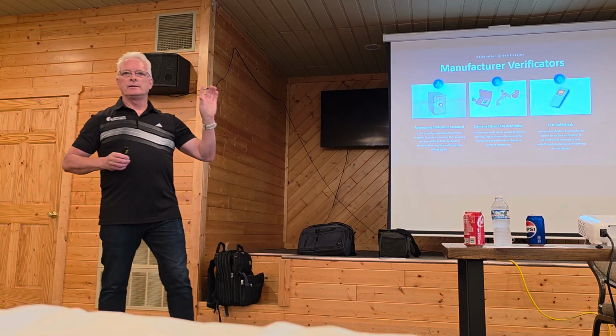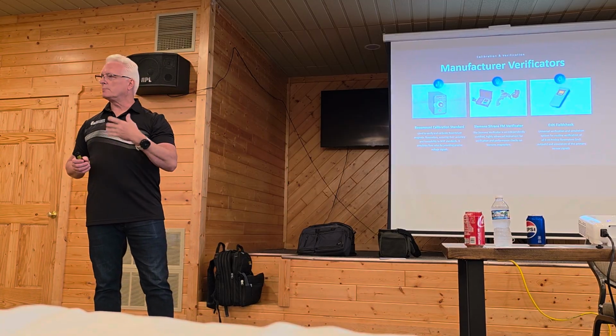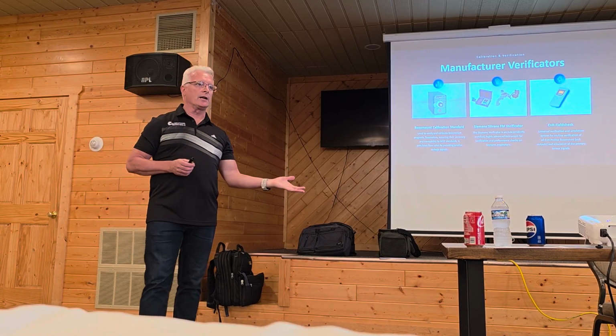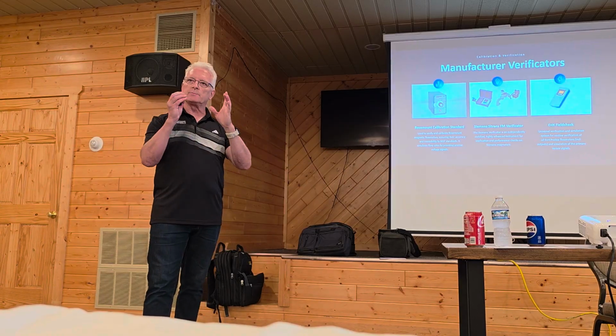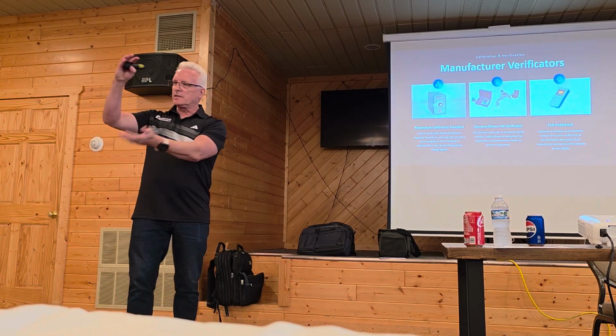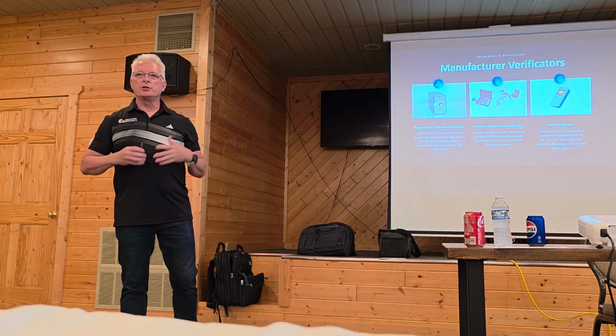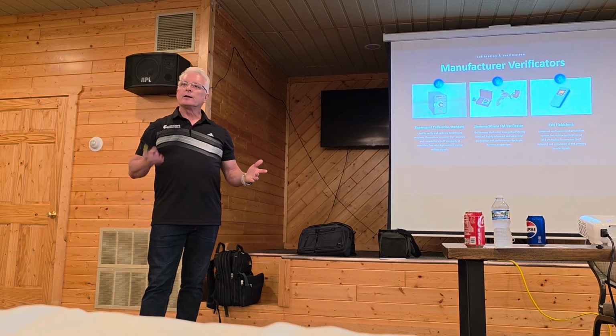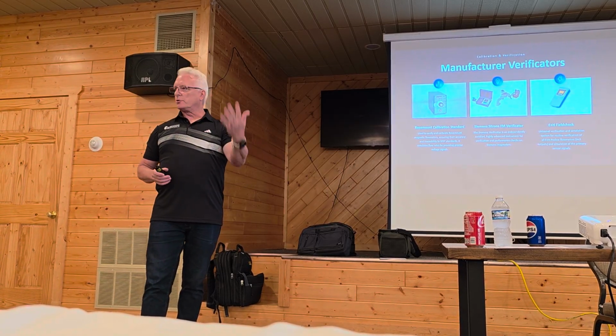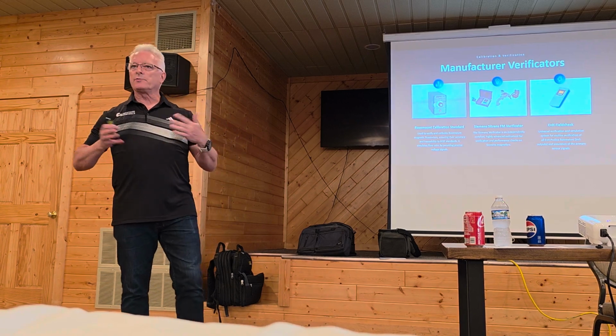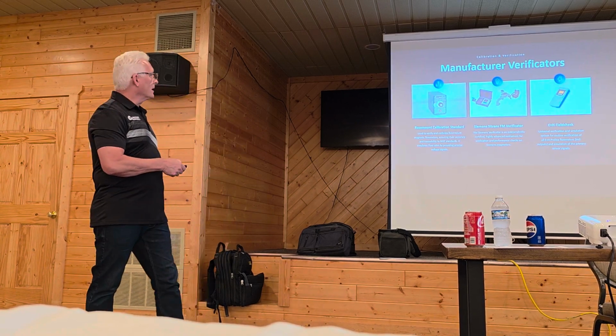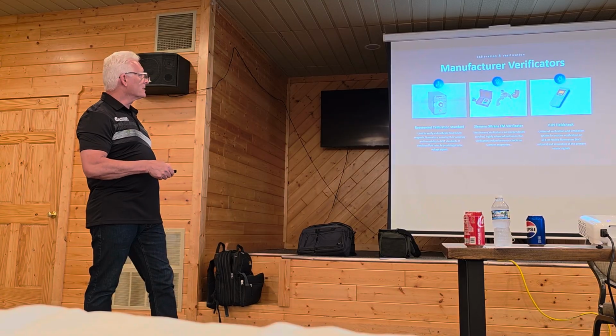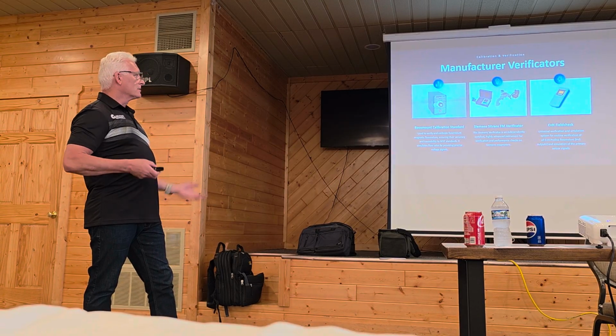So I like the outside device testing, and we do that as much as possible, but we also do the electronic in between a lot of times because it does more of a this whole thing passed, this whole thing passed, this whole thing passed. So you know your meter's working right. And then if there is a problem, now you bring out the analog and you check it. So there's a couple different ways you do them now. And I call that the analog way, and that's this device. This is for Siemens, this is for Endress+Hauser. So those are just examples.